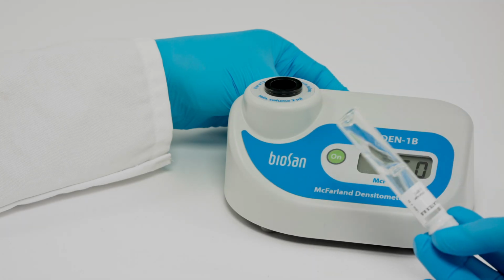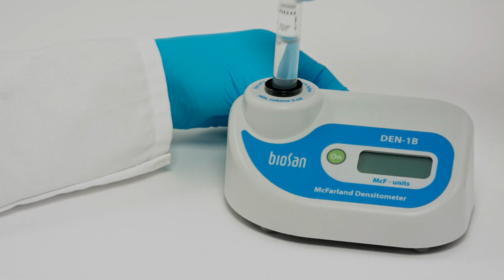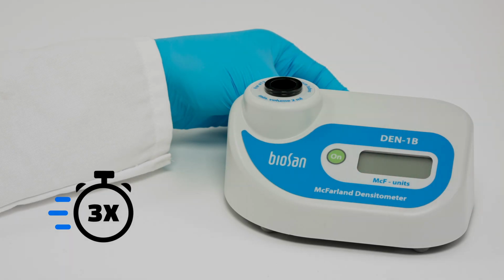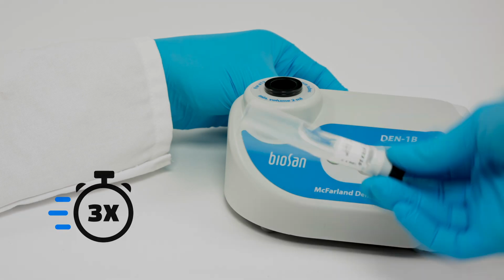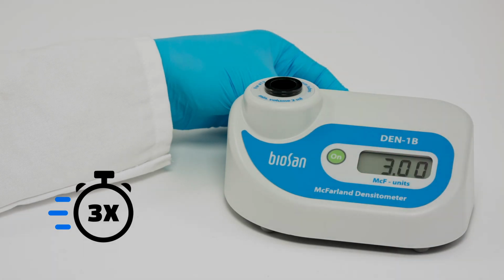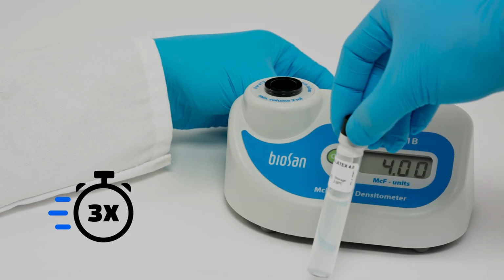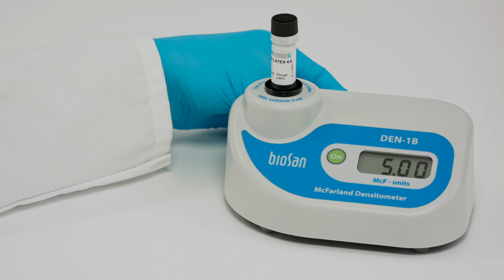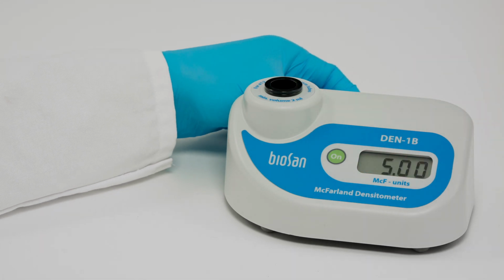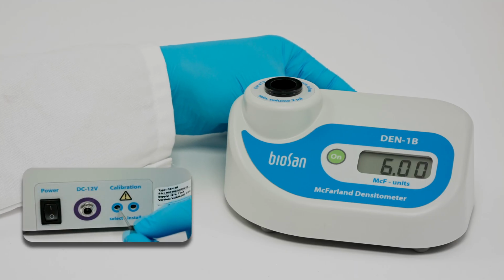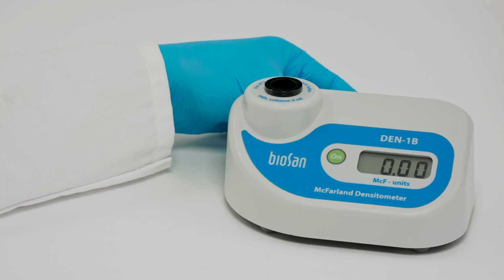Repeat that process until you reach 4 McFarland units standard. In this calibration kit, the 5 and 6 McFarland standards are not available. To skip those, press the Select button. After skipping the last value, unit automatically exits calibration mode and is ready for operation.